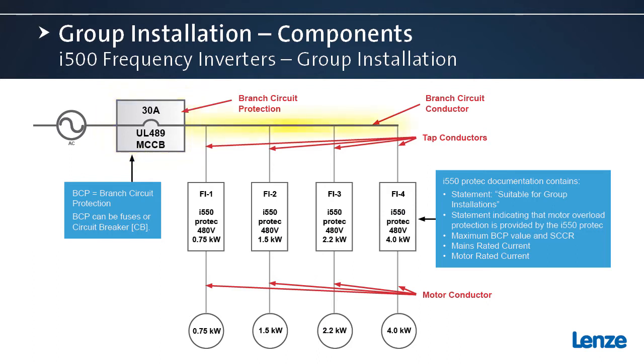The thick black horizontal line represents the branch circuit conductors. The thinner vertical lines that go to each individual frequency inverter, those represent the tap conductors. And then, of course, coming out of each frequency inverter to the motor are motor conductors. The NFPA 70 and NFPA 79 standards both have requirements for sizing the branch circuit protector and these conductors. We'll see that come back in another slide here in just a minute.